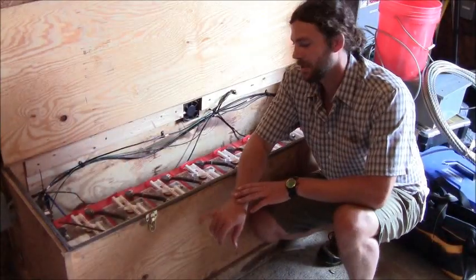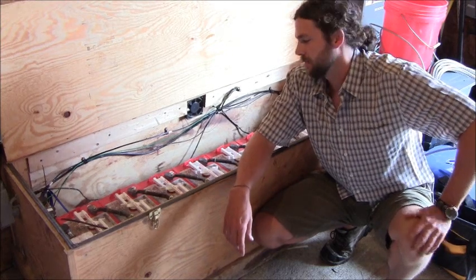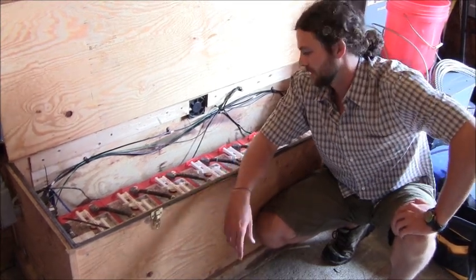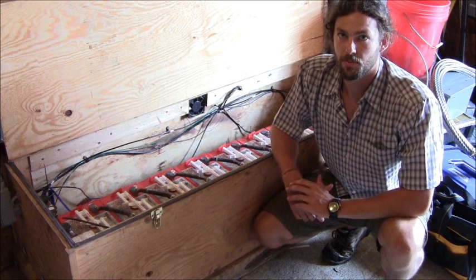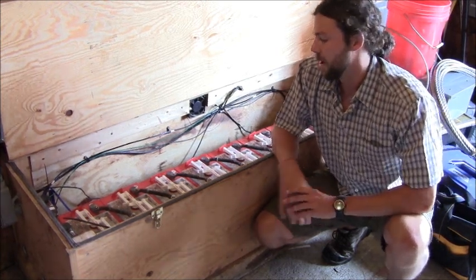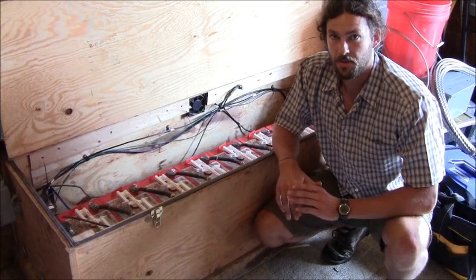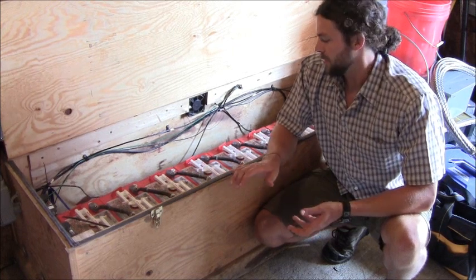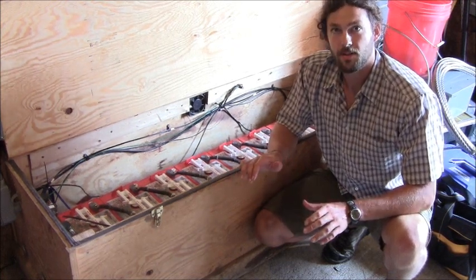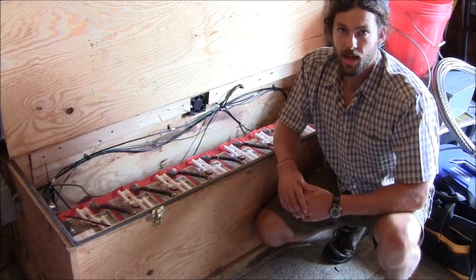Here we have our 48 volt deep cycle lead acid battery bank. These are 6 volt batteries, 232 amp hours each, connected in series. This battery bank is monitored by the MidNite Solar charge controller, which we just wired up. The purpose of the charge controller is to monitor the state of charge of this battery bank — we don't want the battery bank to overcharge or undercharge. Once the batteries are charged to their float charge value, the excess electricity is either dumped to a dump load such as a heater or a fan, or in this case it's sold back to the grid via this inverter here.